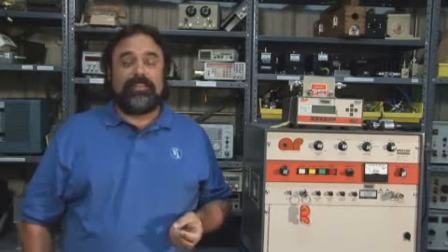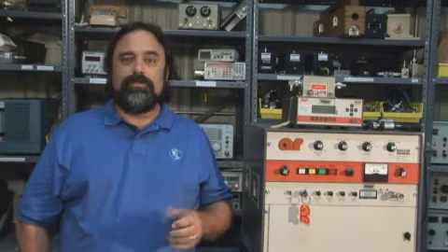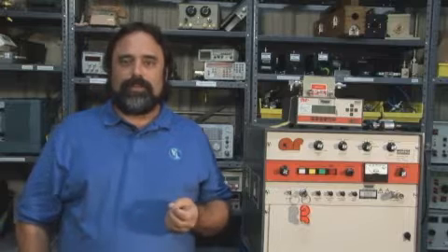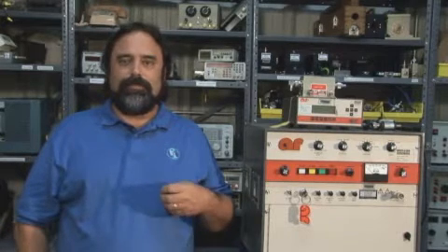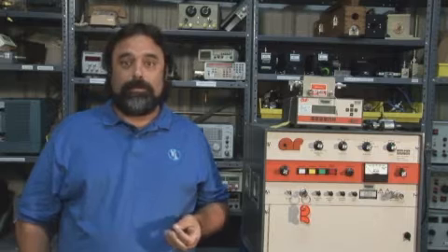The performance criterion C, on the other hand, is the performance criterion for when you do interrupts. For example, you turn the power off for 5 seconds. You can then bring the unit back up and have user intervention to get the unit to operate correctly. For performance criterion C, you're allowed to have some user intervention in order to get the unit operating correctly. Because if you do a 5-second interrupt, for example, you may have to reboot the system. You may have to type in some commands in order to get it back into its normal operating state. This is allowed for performance criterion C.